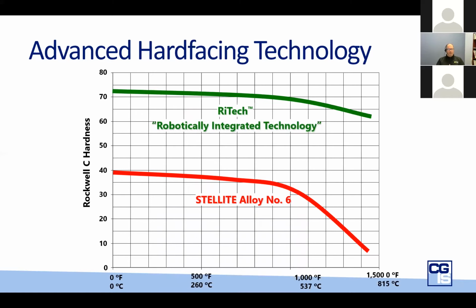So when we start talking about metal-seated valves, we need to realize that metal-seated valves are not created equally. There's a variety of different coatings that are utilized by manufacturers. We have to quite often use dissimilar metals in order to ensure that we don't have any cold welding or galling or marrying. But with hard coatings, we can now look at thermal sprays using tungsten carbide or chrome carbide, which start off with a very high hardness and maintain that at elevated temperatures. So we can see with stellite, we lose our hardness as the temperature ramps up, and that also holds true for electroless nickel plating. ENP does start off harder than stellite, but it still does suffer from temperature effects and softening and losing its hardness.